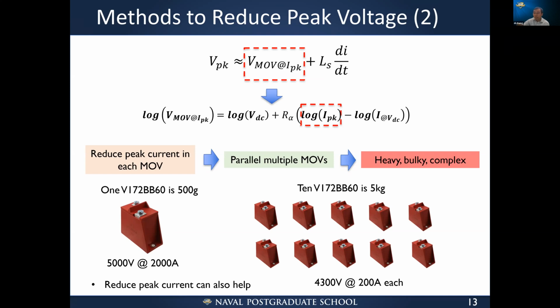Because the system peak current is the same, the more MOVs you put in parallel, each MOV will only share a small fraction of the current. For example, if we have one MOV, 2000 amps is 5000 volts. If 10 MOVs in parallel, you can bring it down to 4300 volts, right? It did go down. However, first it is limited, and also it's quite heavy, bulky, and complex.